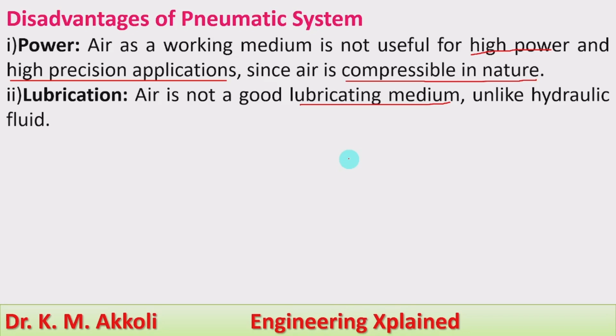Heat dissipation: air, due to its low conductivity, cannot dissipate heat as much as hydraulic fluid. If you apply pressure on the fluid, its temperature will increase, and it will carry the heat and dissipate it to the atmosphere or other components in a low temperature region, as takes place in the hydraulic system. But in the pneumatic system, because of the low conductivity of air, it will not transfer the heat as much as in the hydraulic system. That's why separate heat exchangers are used, and it should be ensured that whatever heat is generated in the system is dissipated.